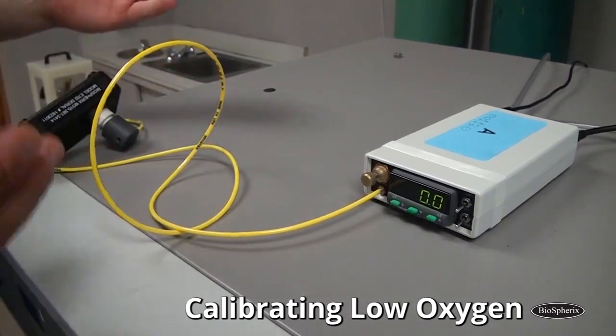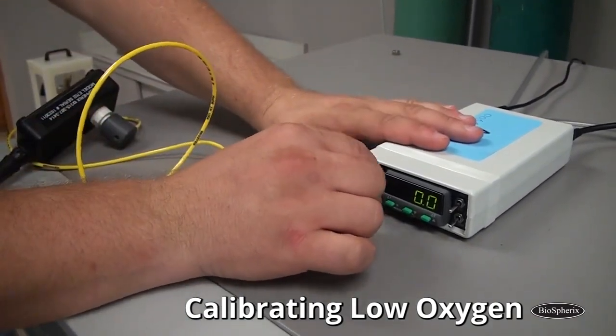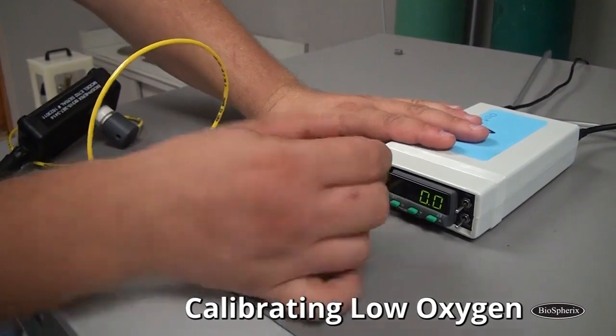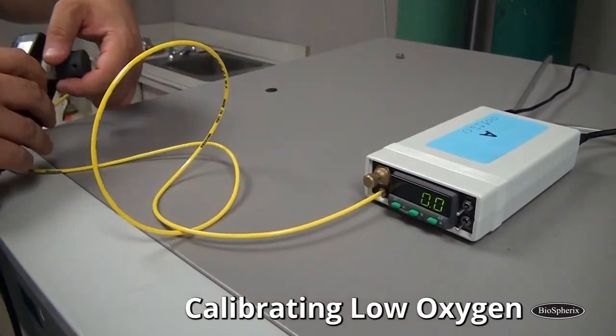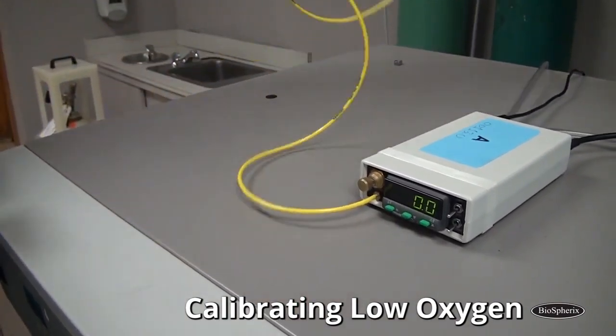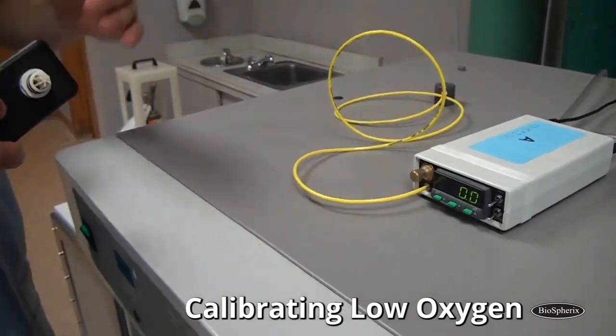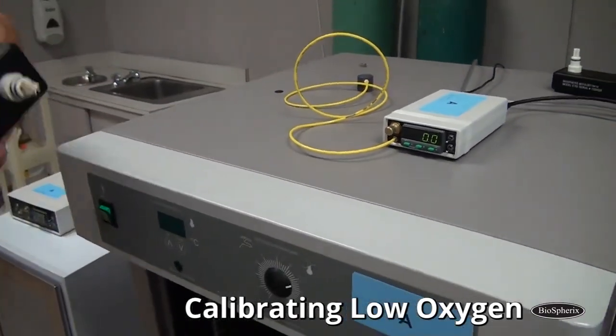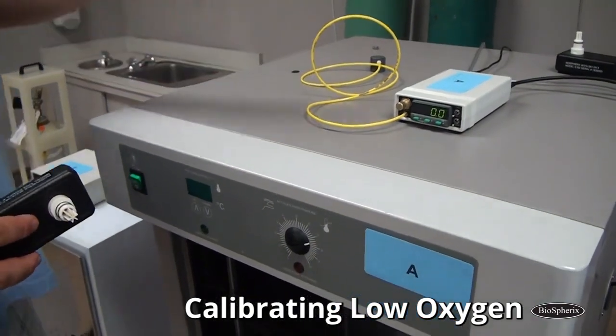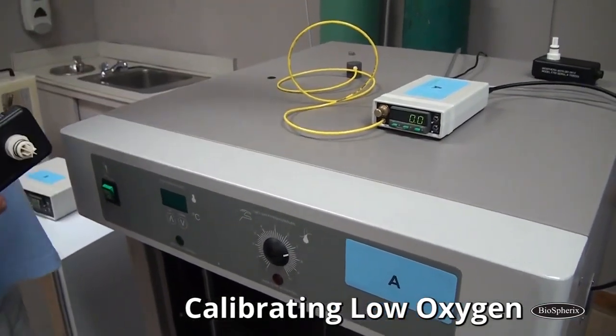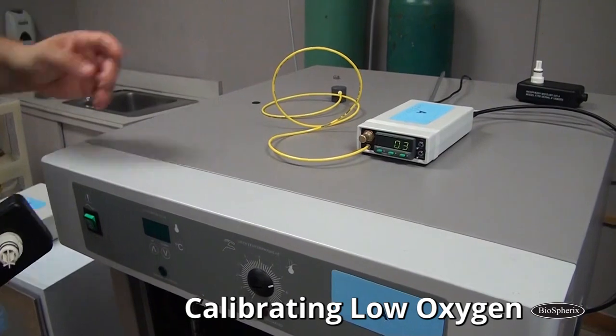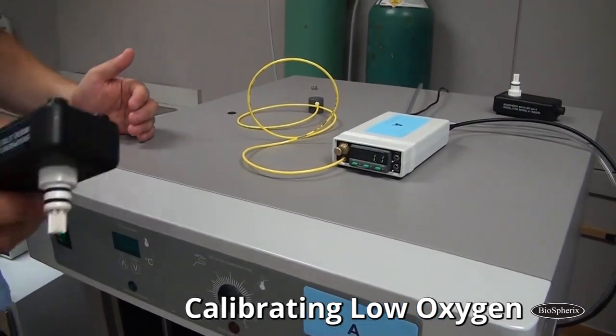Now that we're at 0, we're all good. We're just going to turn the gas off by closing the bleed valve. I'm going to take the sensor tip off here. We're done with our 0 calibration. Again, it's a 2-point calibration: a low, our 0, and then our high, span. So now we're going to do a span, our high level, which is going to be room air.